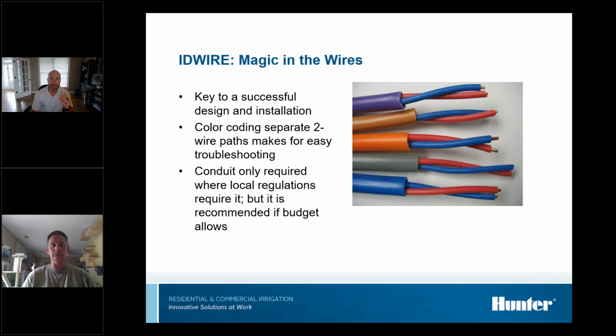We talked about the wire, so here's what this stuff looks like. I can't stress enough how key specifying and designing the proper wire is to a successful design and install. Color coding makes it easy to separate the 2-wire paths for troubleshooting. It's got that outer protective jacket available in a wide variety of colors. You can get this from Hunter, we have part numbers for it, and there are other wire manufacturers that make the same thing. You just need to make sure it meets Hunter specifications. Conduit's not required by Hunter, it's only really required if you're working within a municipality that requires it, which is pretty rare.